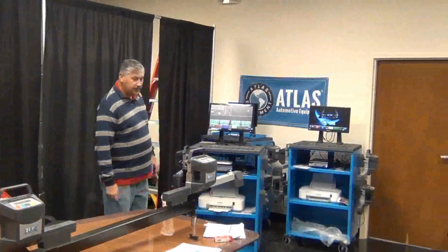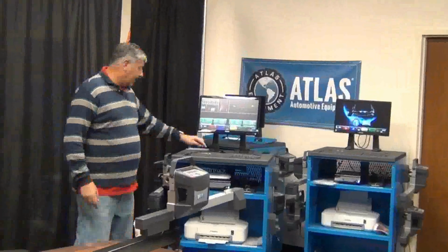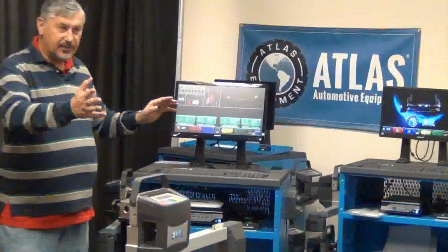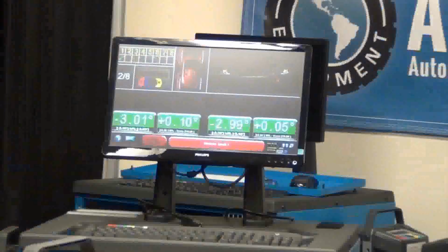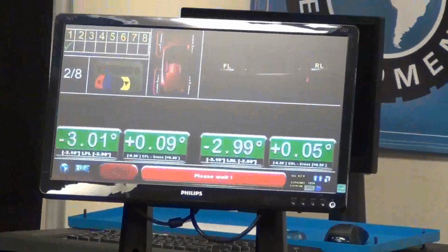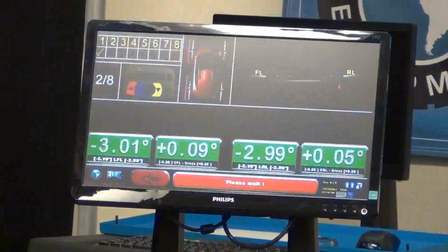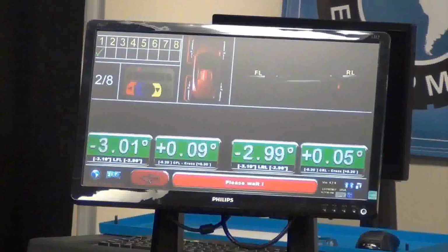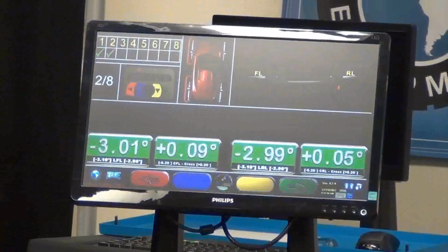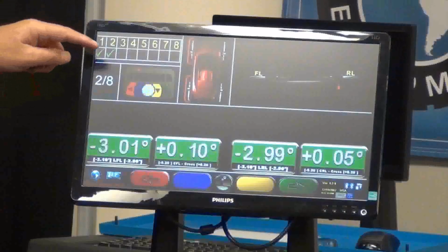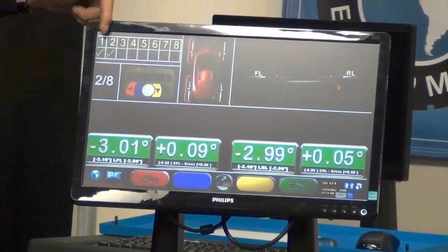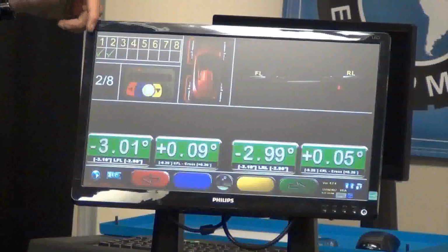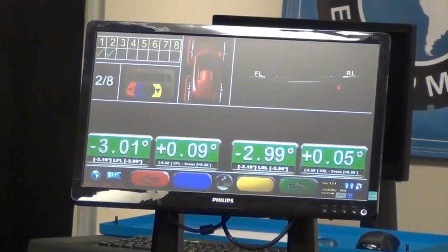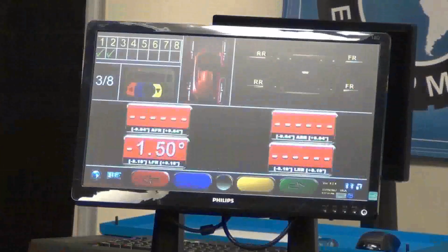The machine is now asking me to push the black button, or I can push the F5. F5 and the black button have the same representation. They both operate the same feature. The machine says to you wait, so you wait for a moment while the calibration is accepted by the sensor. The check mark will now appear at number 2. We now have 2 check marks. So the first part of the calibration and the second part is now being accepted on those 2 sensors. We now hit the green button to progress to our next step.